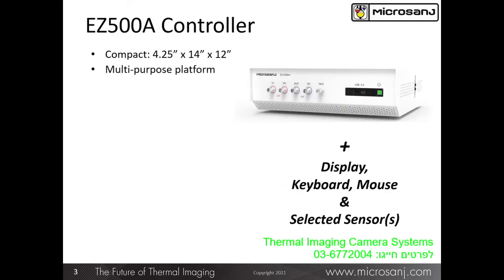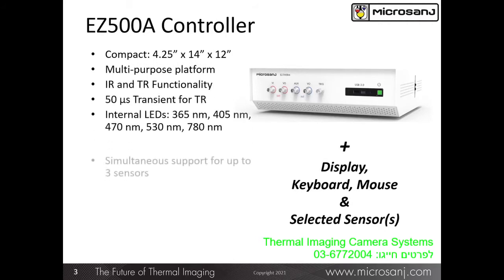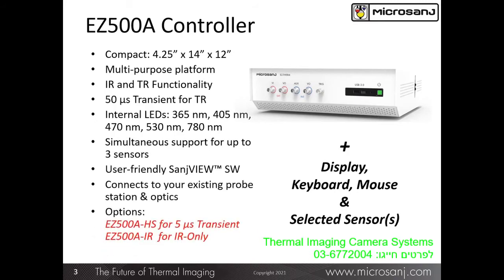The heart of the EasyTherm system is the EZ500A controller. This module contains all the essential electronics, illumination sources, and computer with the embedded SanjVIEW software. Not shown are the display, keyboard, mouse, and sensor. The controller has a small 14 by 12 inch footprint. It is a flexible platform with the ability to support both infrared emission and thermoreflectance-based imaging. The transient response for TR imaging is 50 microseconds, and several wavelengths are included for illumination sources for TR mode. The EZ500 can simultaneously support up to 3 sensors, and it contains the field-proven, user-friendly SanjVIEW software. And it can be connected to your existing semiconductor test equipment, saving additional investment for equipment you already have.